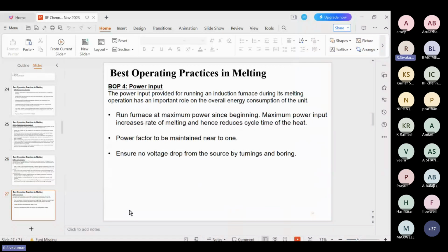The power input provided for running an induction furnace during the melting operation is also very important. In few industries during our audit, we found the maximum demand, the sanctioned demand, is lower and not optimized. That is the reason a 750 kilowatt furnace may be operated at 600 kilowatts. So definitely the melt time is increasing, and due to that the energy consumption is also increasing.